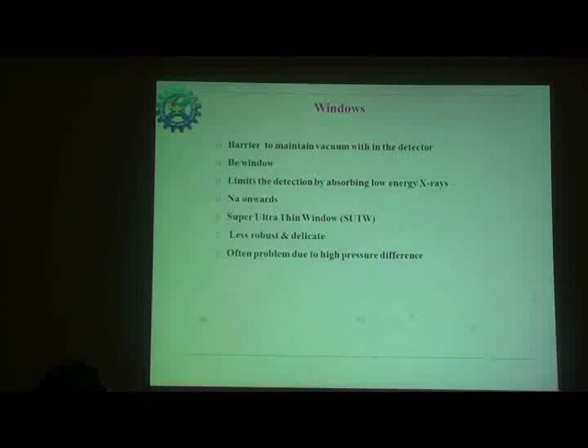So when you are working in very high vacuum, and you open the specimen chamber for sample loading, you create a lot of pressure inside the column, and there is a vacuum inside the detector. This pressure difference can break the window, which can puncture, and the whole detector will go bad. So you should be very careful when you do the sample loading.